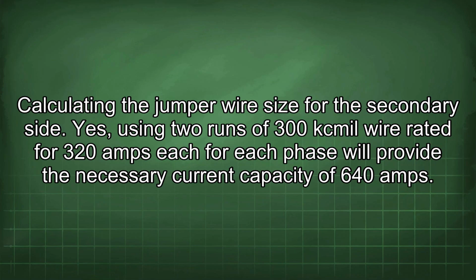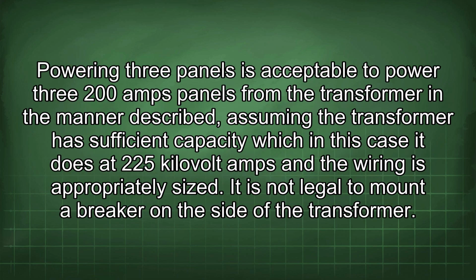Calculating the jumper wire size for the secondary side. Yes, using 2 runs of 300 kcmil wire rated for 320 amps each for each phase will provide the necessary current capacity of 640 amps. It is acceptable to power 3 200 amp panels from the transformer in the manner described, assuming the transformer has sufficient capacity, which in this case it does at 225 kilovolt amps, and the wiring is appropriately sized.